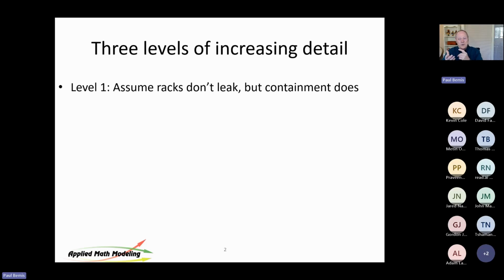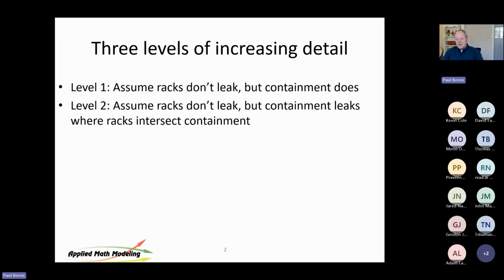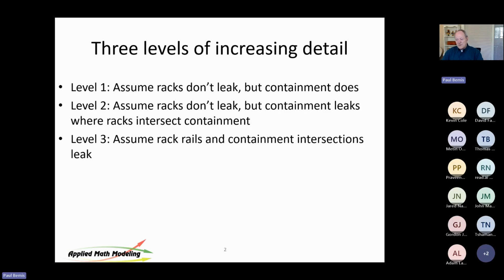So over the years we have gotten comfortable with a certain level of detail for getting answers out of this system with CFD. And there's 3 levels you can work with depending on your needs. Level 1 is assume the racks don't leak at all, but the containment does. The second level is assume the racks don't leak, but the containment leaks where it intersects the containment. And the third one is assume everything leaks.